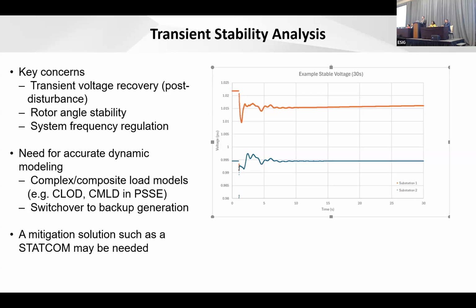And definitely the switchover piece becomes very critical. When we do this analysis, if we see there's going to be an issue, you can do some things—you can go in for faster breakers, for example. But if even that doesn't help, then you can go with something like a StatCom, and this is a utility StatCom I'm talking about, not the industrial one we talked about for flicker.